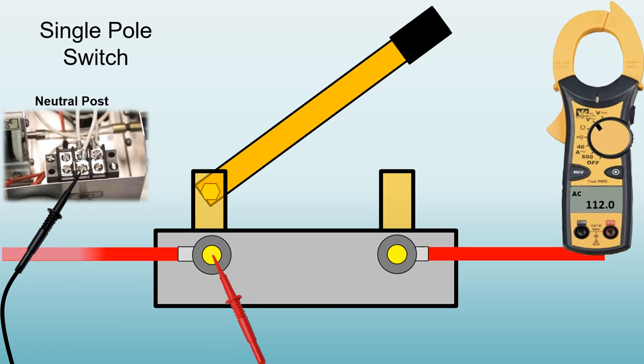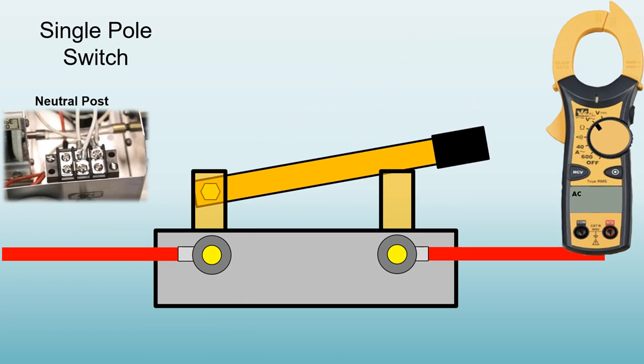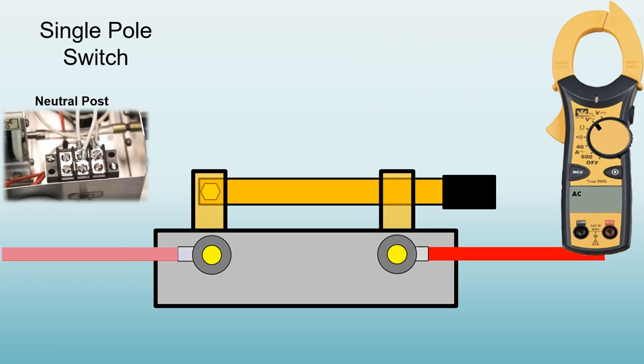Let's show how this works on a single pole switch. We have current flowing through on the left side. We take one of our meter leads, we set it to AC current. One goes on the switch where the current's coming in, and a negative to our common or our neutral pole. And again, remember, you can connect to any white wire in the machine to grab a common. This shows our voltage coming through.